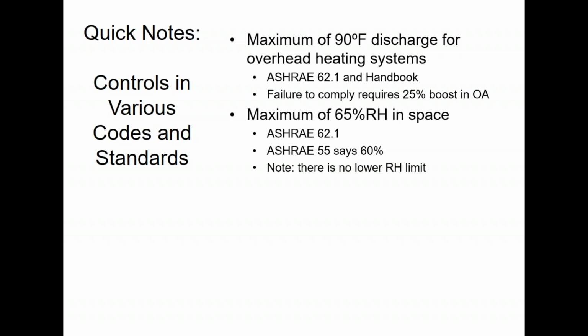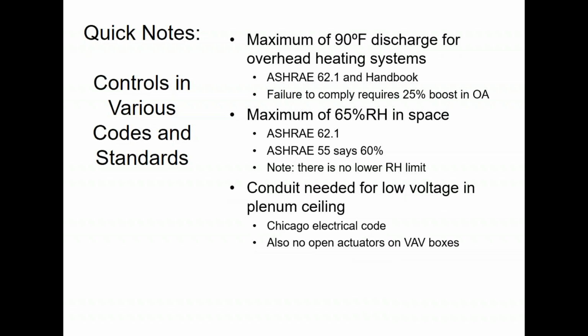You can slow fan speed down. You can add an ERV. You could control humidity on demand as opposed to just temperature only. So those kind of things. There is no lower limit from any of the ASHRAE standards for relative humidity. Only upper limits, no lower limits. There used to be a lower limit of 30%. That got eliminated over 10 years ago. I don't remember why, but there's no lower threshold.